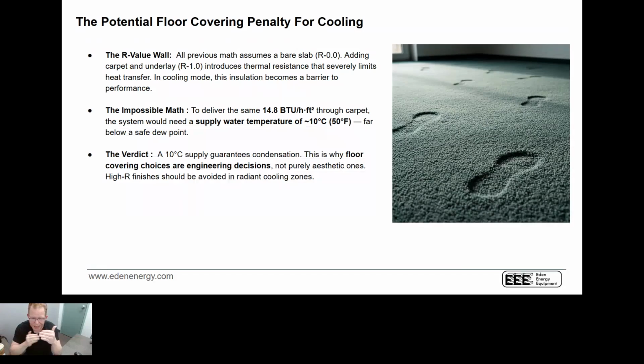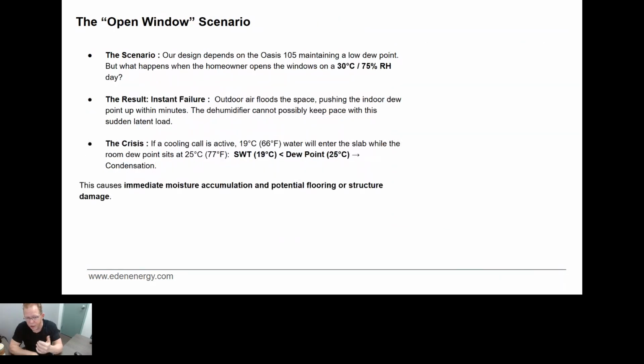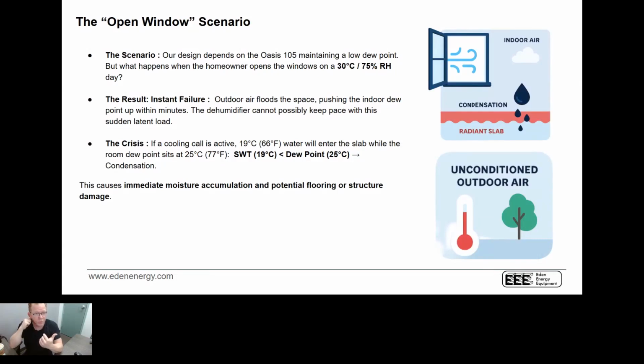So we need to understand a lot of things with radiant cooling. What is the actual humidity in the space? How are we going to control that latent cooling? How many BTUs do we need? And what kind of floor finishings are going to be in that space? If we design a system around tile and it ends up not being tile, it's going to be a problem.